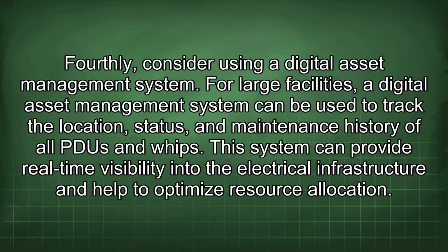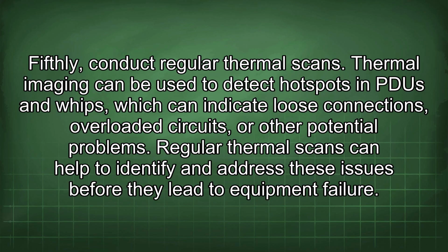Fourthly, consider using a digital asset management system. For large facilities, a digital asset management system can be used to track the location, status, and maintenance history of all PDU and whips. This system can provide real-time visibility into the electrical infrastructure and help to optimize resource allocation. Fifthly, conduct regular thermal scans. Thermal imaging can be used to detect hotspots in PDU and whips, which can indicate loose connections, overloaded circuits, or other potential problems. Regular thermal scans can help to identify and address these issues before they lead to equipment failure.